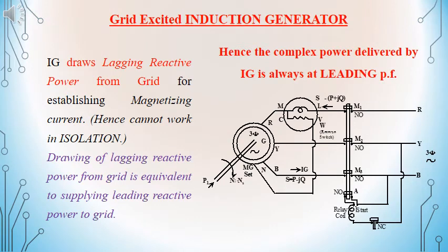The medium of energy conversion between the mechanical energy and electrical energy is a magnetizing system. In order to have the magnetizing current, there should be a lagging power that is drawn from the supply system or from the grid for an induction generator. Drawing a lagging reactive power from the grid is equivalent to supplying a leading reactive power to the grid. Because of the same, the grid excited or separately excited induction generator will always be operating at a leading power factor.